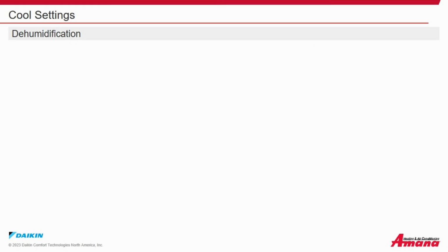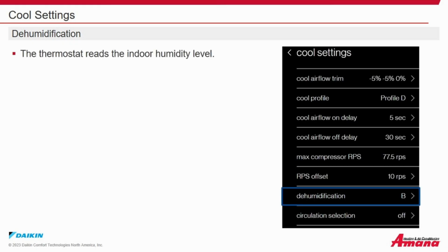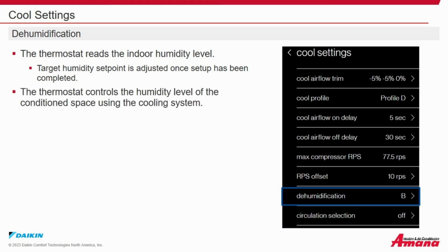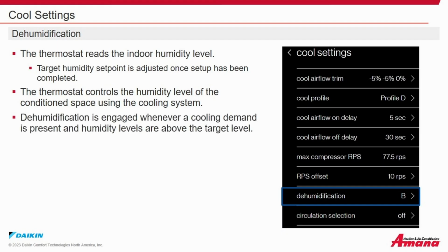Cool settings. Dehumidification. The thermostat reads the indoor humidity level. Target humidity set point is adjusted once the setup has been completed. The thermostat controls the humidity level of the conditioned space by using the cooling system. Dehumidification is engaged whenever the cooling demand is present and humidity levels are above the target level. The circulating fan output is reduced. The system runtime increases.